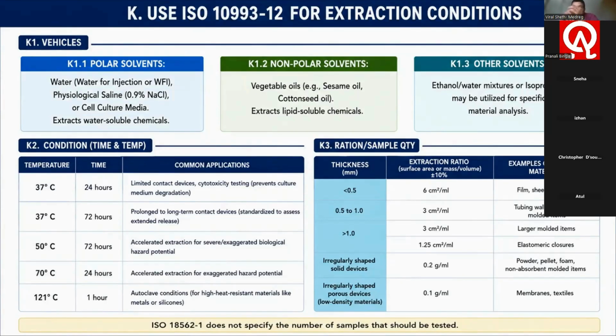Second thing, same scenario for the infusion sets. The internal lumen of the device is mainly what comes in contact with the patients. But laboratories are directly cutting your tubes and doing the testing. My question, or one risk I identified, is that you must do an extraction of the internal surface of your device only, irrespective of the external surface, because during manufacturing so many operators touch the external surface of your devices. So there may be some other biological risk, but that is not going to the patient. So there are chances of false positive results. So you should also understand which part, inner or outer, is coming in contact. That is also a crucial part to understand for the extraction condition.